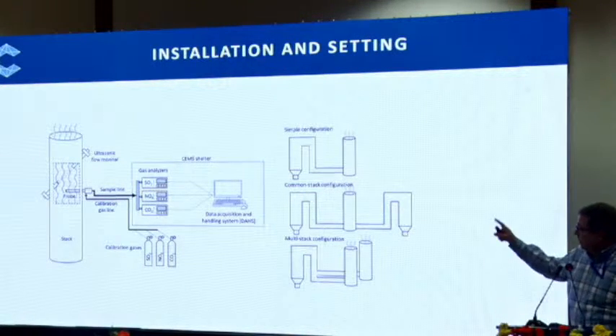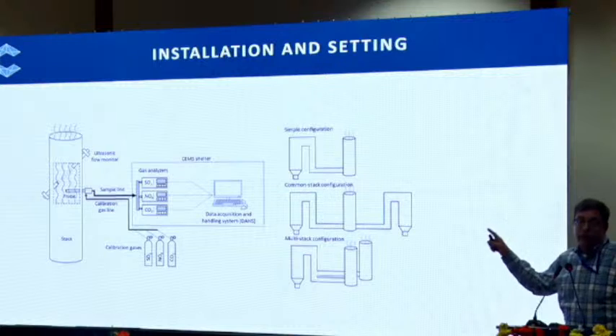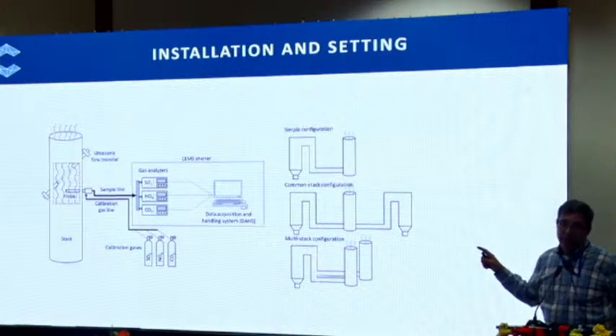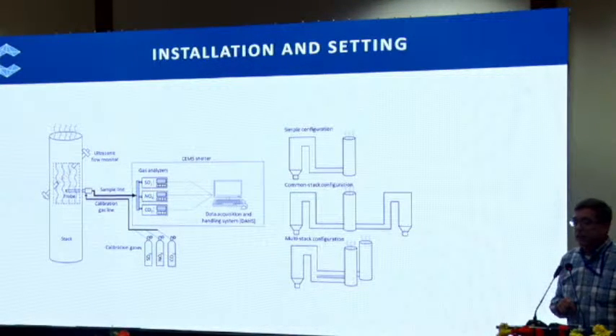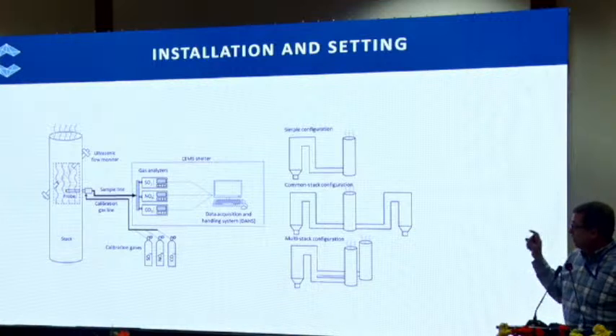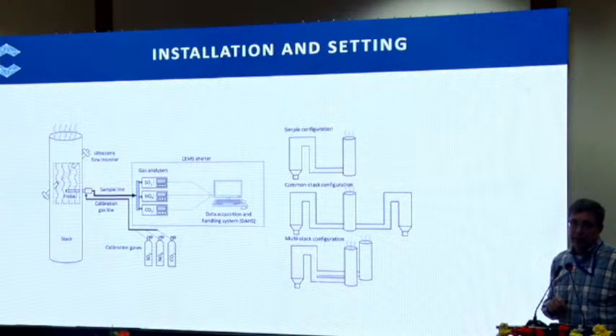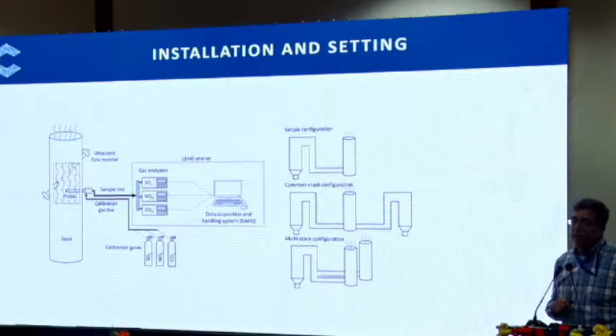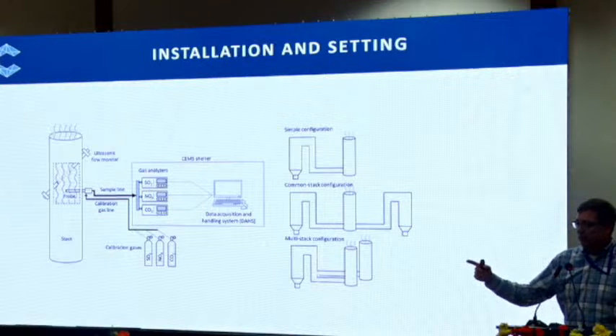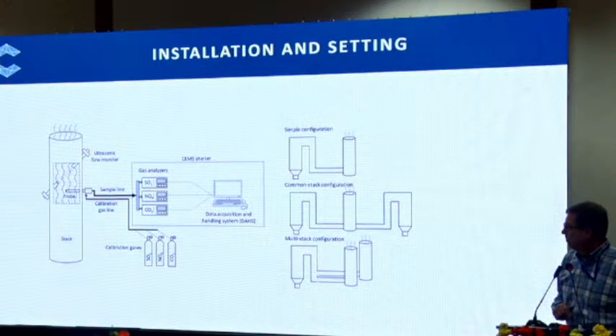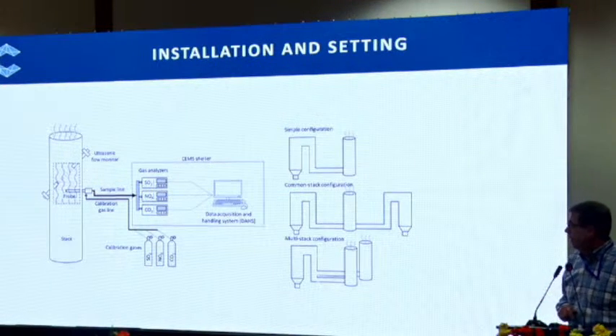So you're measuring with the ultrasonic flow meter. You can either use ultrasonic or you can use an S-type pitot, depending on your stack configuration. Ultrasonic monitors are limited on their insertion depth, so if you have extremely long port depths, you would not be able to use that. So you would use an S-type pitot.